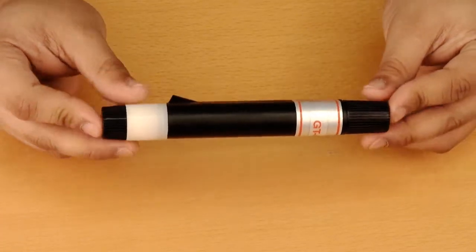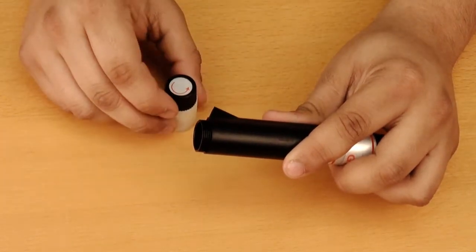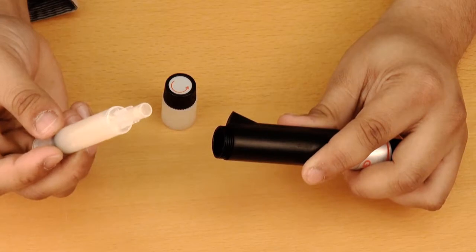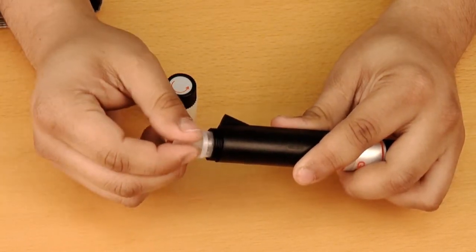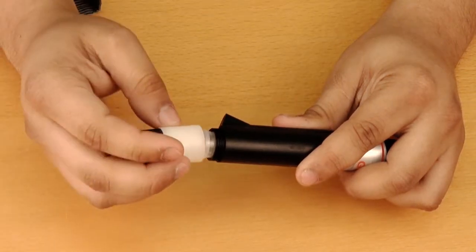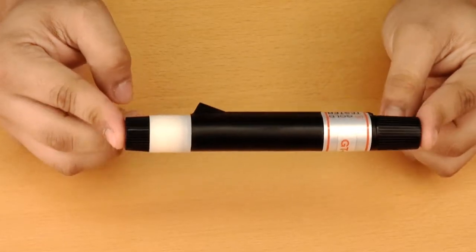Unscrew the rotating cap at the top of the sensor probe to open the probe for refill insertion. After removing the plastic cap from the tube nozzle, insert the tube into the sensor probe so the nozzle faces down and the stem faces up. Place the rotating cap ensuring that the gel refill stem is going into the slot on the rotating cap. Use tester as per tester's manual.